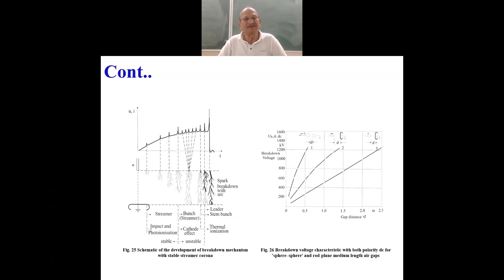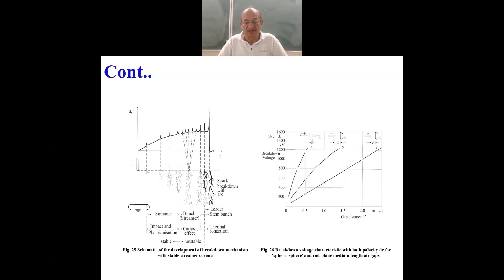When you increase the gap distance further, the field is rendered no more uniform because of the space charge effect and larger avalanches. Above 2 centimeters of gap distance, the space charge effects become significant and the field becomes weakly non-uniform, measuring something like 25 kV per centimeter.